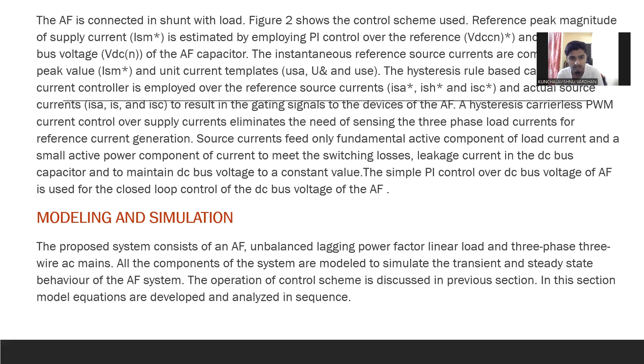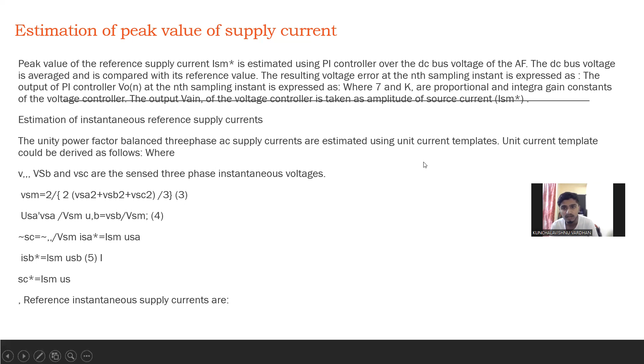The peak value of the reference supply current is estimated using a PI controller over the bus voltage of the AF. The DC bus voltage is averaged and compared with its reference value. The resulting voltage error at the nth sampling instant is expressed, and the output of the PI controller V naught of n at the nth sampling instant is expressed in terms of Kp and Ki, where Kp and Ki are the proportional and integral constants of the voltage controller. The output of the voltage controller is taken as the amplitude of the source current. Estimation of instantaneous reference supply current. The unity power factor balanced three-phase AC supply currents are estimated using the current templates. Unit current templates could be derived as follows.